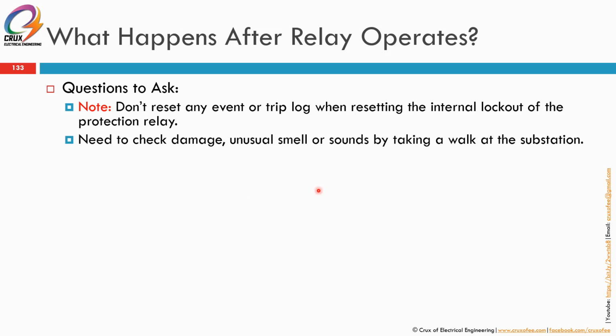So normally after relay operate, you would see whether this is a feeder going to a transformer, a feeder going to a motor, or a feeder going to switchgear. So you have to check the damages. Go to the location of the switchgear, go to the location of the motor, transformers, or equipment, capacitor banks. Note any unusual smell or sounds by taking a walk around the substation.